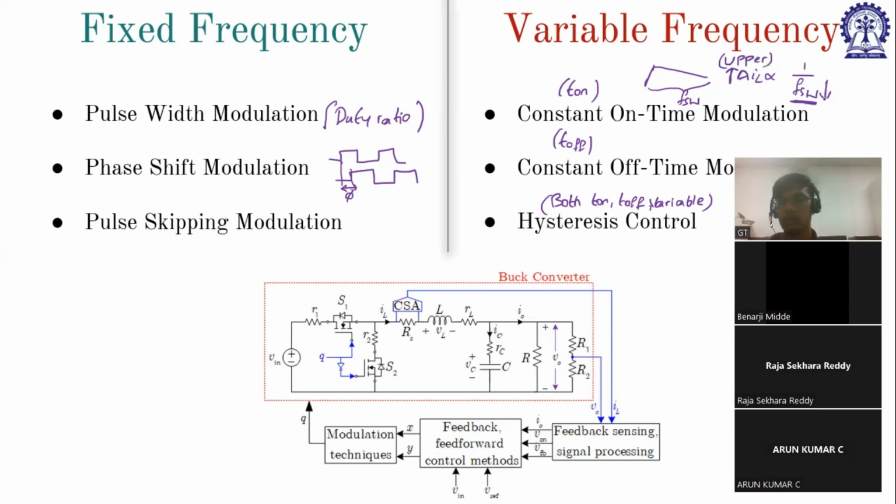It also has a higher limit on the FSW. And what's the purpose? You cannot operate it at a very high frequency, right? It again boils down to the architecture and the hardware that you are concerned with. So there will still be some limitation. Again, the frequency comes from the input and output voltage that you are selecting.